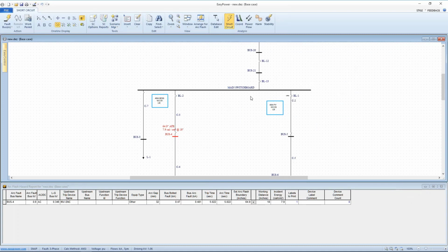Now, the other, and I have this, you can see there's about 1/10 of a calorie difference if I include the PV side when I'm doing each leg incident energy calculation. The point I wanted to make is that there also is a potential for evaluating scenarios that include one or both of the other two power sources.